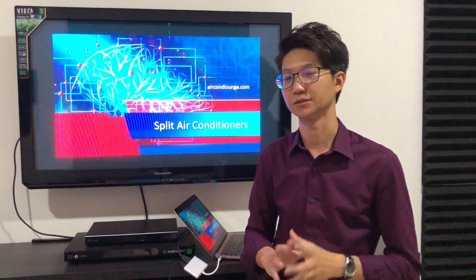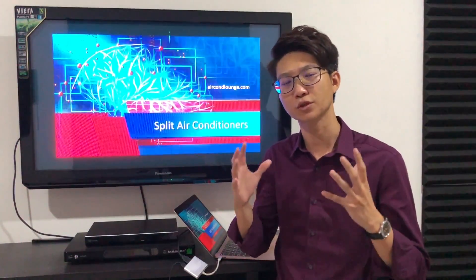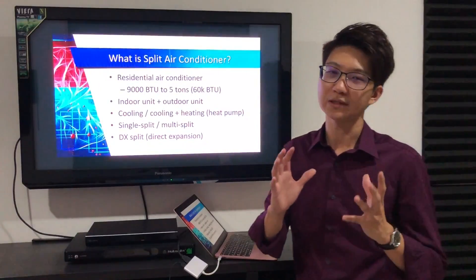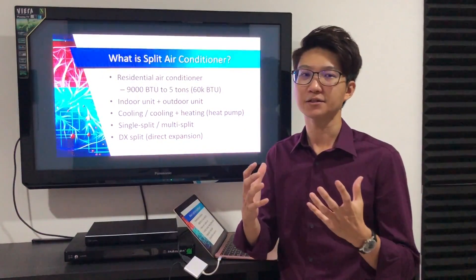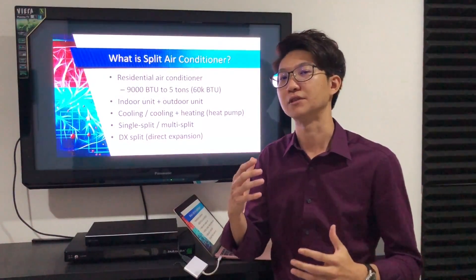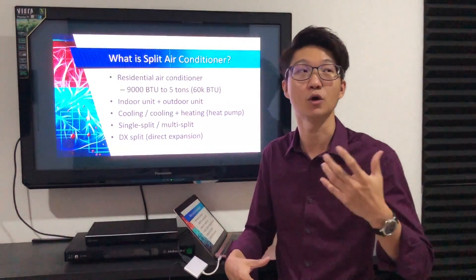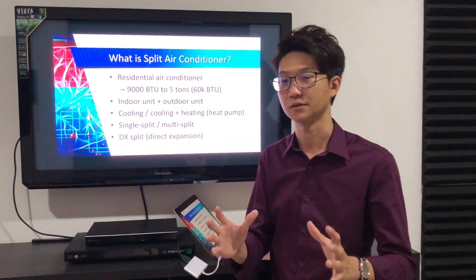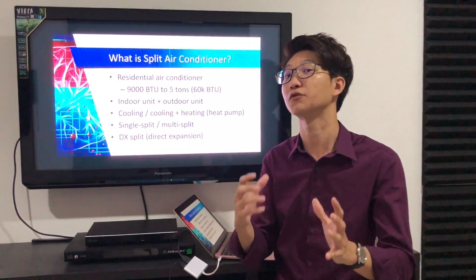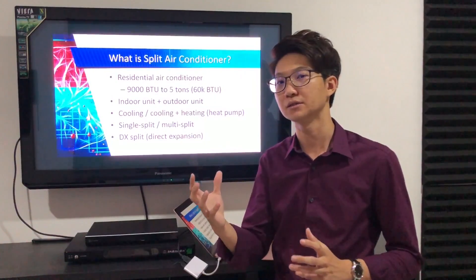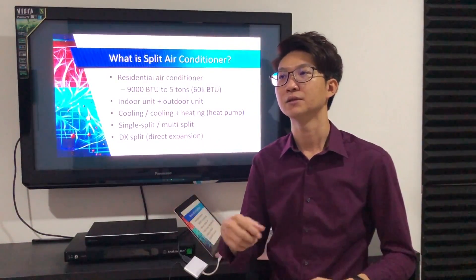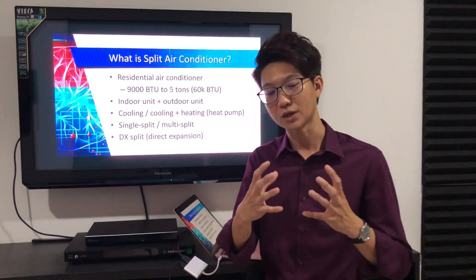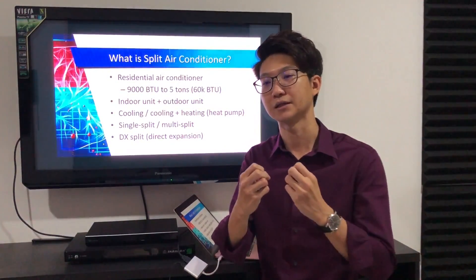There are many types of air conditioner, but today we are going to talk about the most common type — the split air conditioner. Split air conditioners are most commonly used in residential applications, like home air conditioners. Their capacity is usually on the low side, around 9,000 BTU up to 5 ton. The 5-ton unit is about 60,000 BTU — those are for what we call the centralized split air conditioner, where one 5-ton unit supplies the whole house.